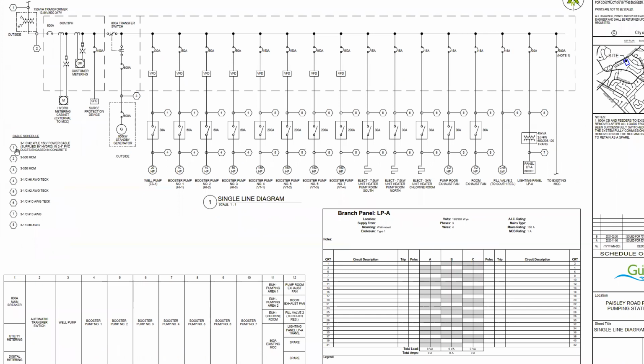Here you can see that instead of calling out on every single one of the lines what the wires are, they have these little hexagons that detail how many conductors and how big they are for the different runs of wire. So that's an 8 and that's a 6, 6 being 3 plus 1 conductor, number 10 AWG TECK. TECK is a specific type of cable that comes with armoring around it.